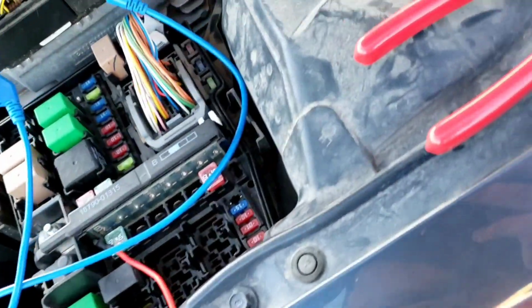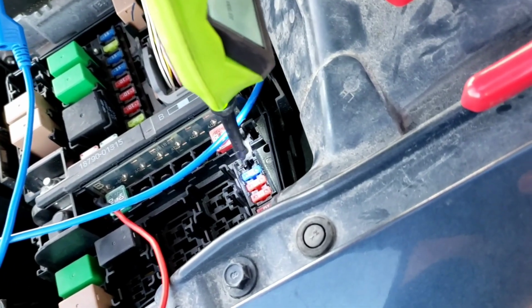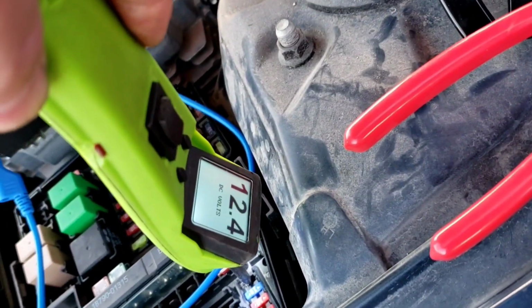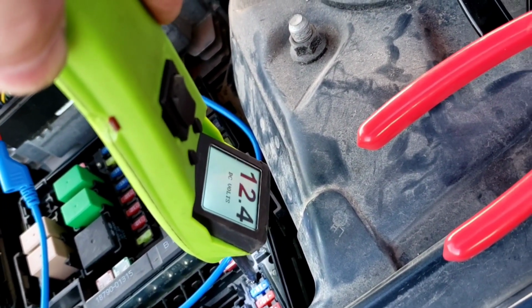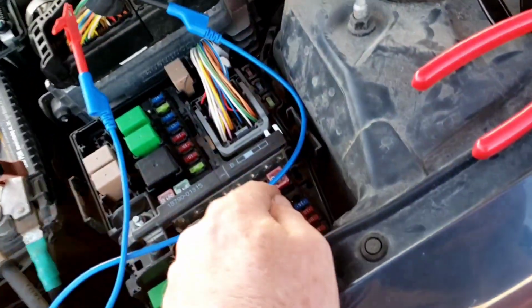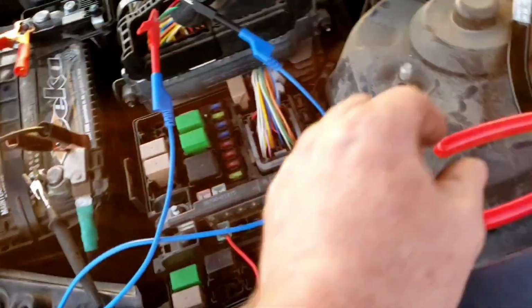We should have no power on that back, but we do, look, there's power on the back, 12.4 volts. We shouldn't have any power back there because the key's off. If I plug it back in, it's going to energize that relay.